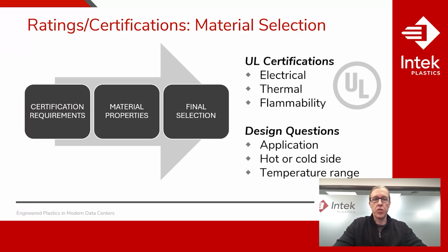Each polymer's molecular structure affects how it performs under thermal, mechanical, and environmental stresses. Some key questions to guide the decision include: where is the component being used? Is it structural, airflow, or electrical insulation? Is it located in the hot aisle or the cold aisle? Those temperature deltas matter. What temperature will it see in regular operation? Understanding that max-min temperature ensures the material won't soften, creep, or crack. This structured approach ensures compliance, performance, and long-term reliability in data center applications.